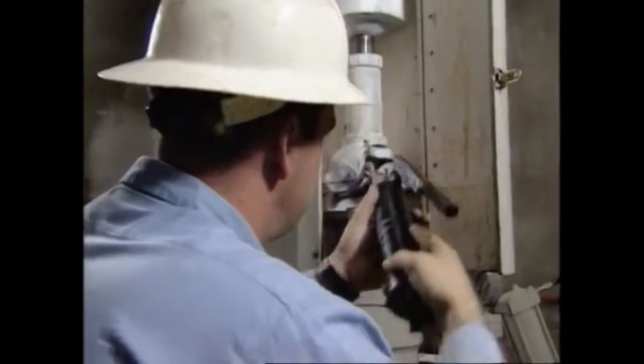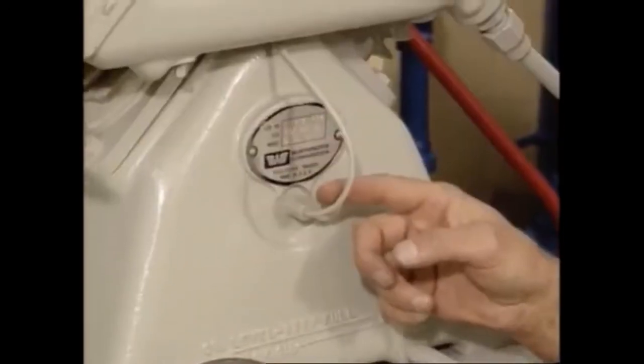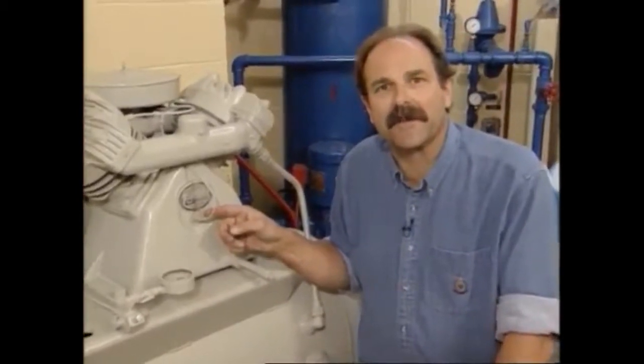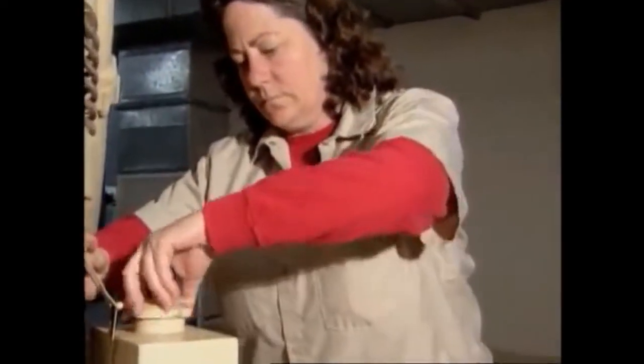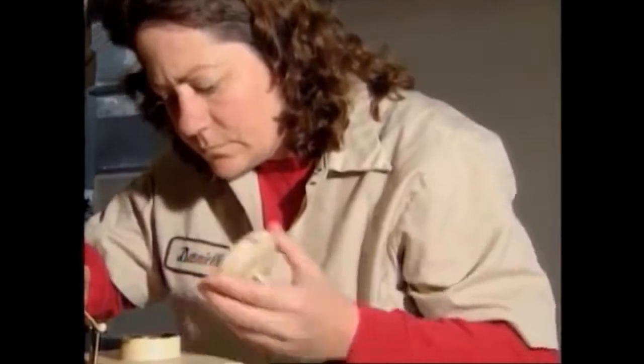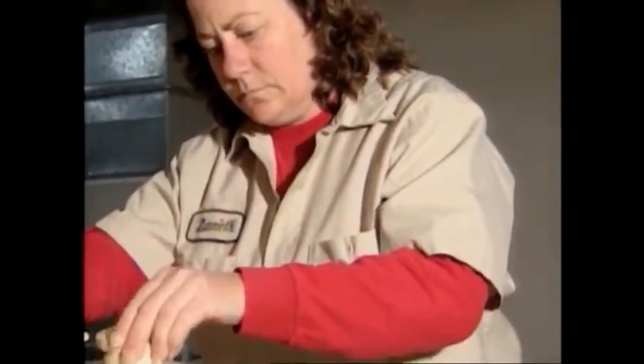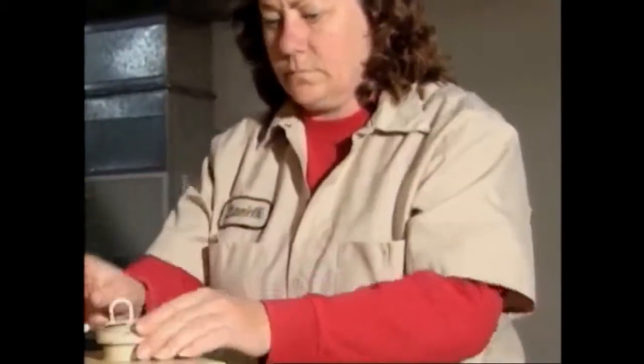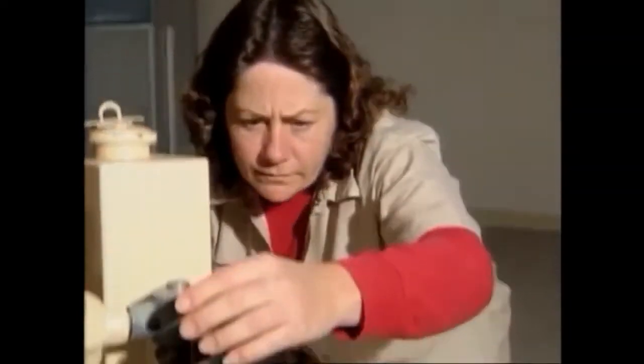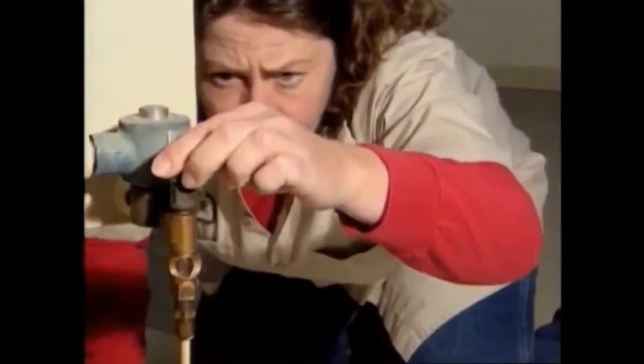Lubrication of equipment is probably one of the most important phases of a maintenance operator's job. Improper lubrication or the lack of lubrication is the major cause of compressor failure. Most compressors require oiling of the bearings. They can have crankcase reservoirs, oil cups, grease fittings, a pressure system, or a separate pump. Whatever type, it must be inspected daily.